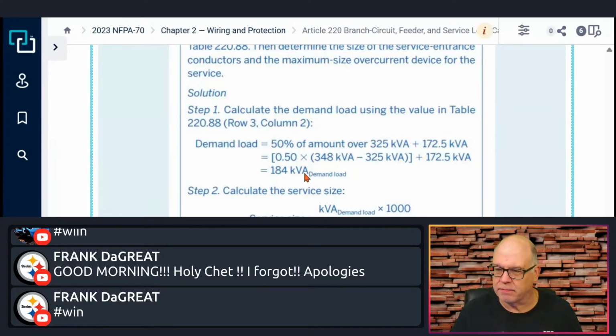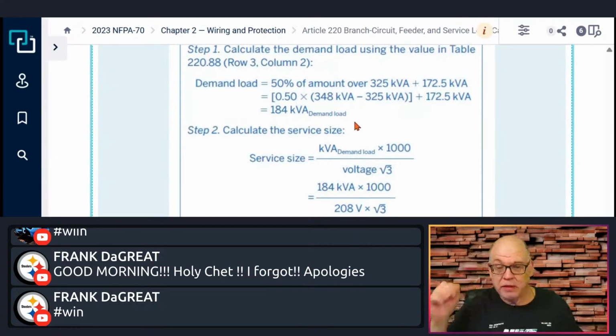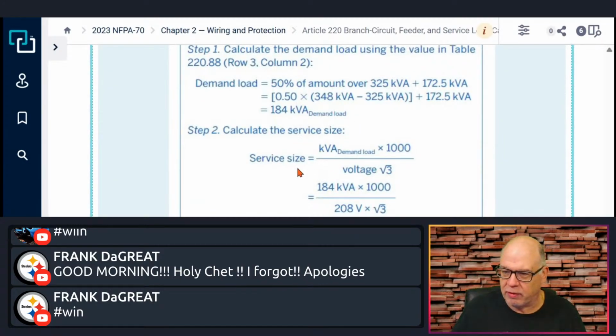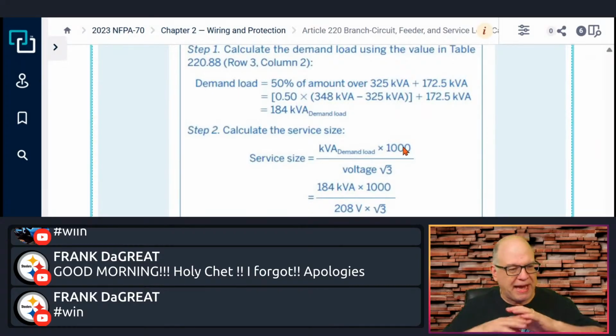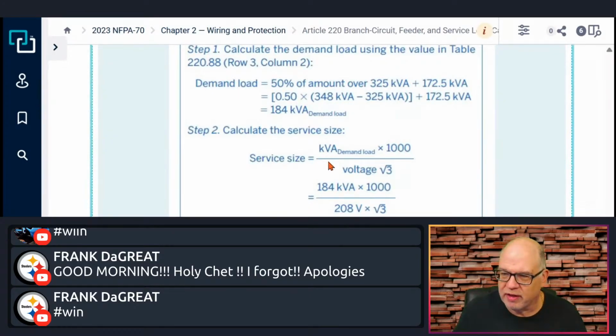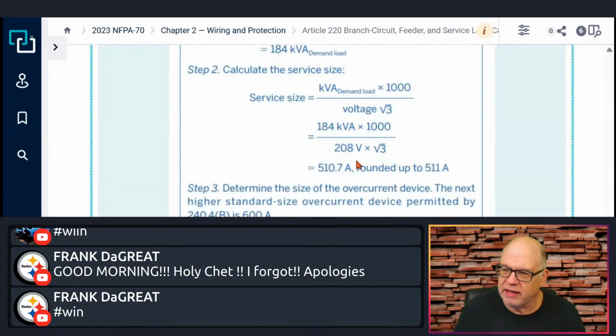All right. Now, that was step 1. Next is sizing the service. So kVA, that's the demand. That's what we just calculated in this example, 184, times 1,000, we get it back to the full amount. But we know that it's 184,000 VA. So here it is, 184 times 1,000. We'll just do that on the calculator since that's the way they do it. Again, we already knew it was 184,000. Skip a step there if you want.